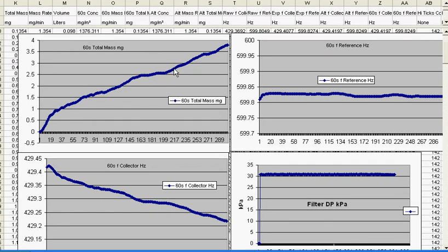This total mass is corrected on by the change in pressure of the filter. As the pressure loads up, the pressure within the collection volume decreases, thereby decreasing the mass of the resonant structure. So now you have an overview of that.